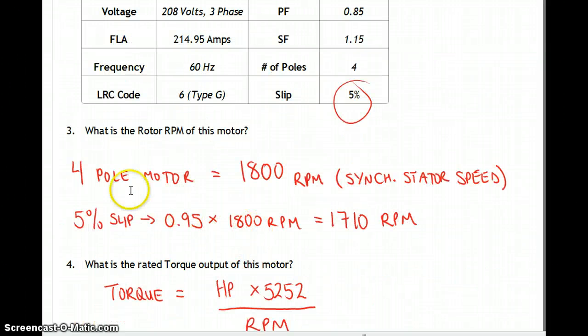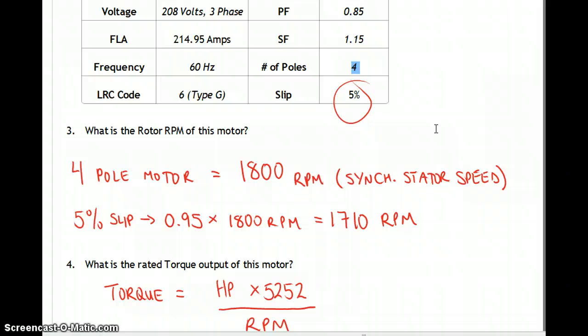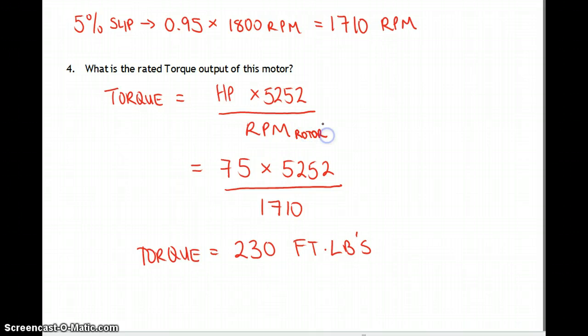Rotor RPM: it's a four-pole motor, so synchronous stator speed is 1,800 RPM. Slip is 5%, so the rotor runs at 95% of that — 0.95 times 1,800 equals 1,710 RPM. Rated torque: horsepower times 5,252 over rotor RPM — use rotor RPM because that's the component doing the work, not the stator. 75 times 5,252 over 1,710 gives 230 foot-pounds of torque.